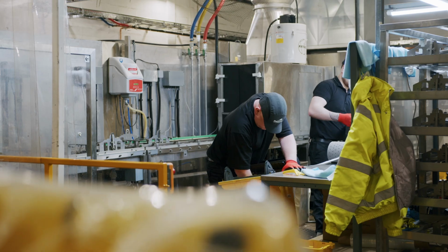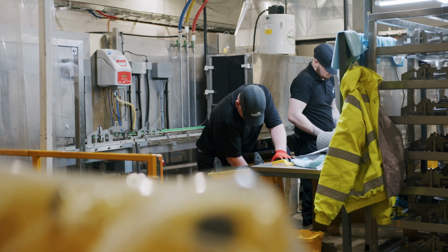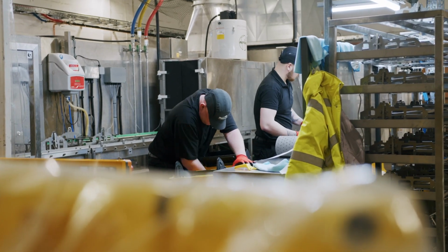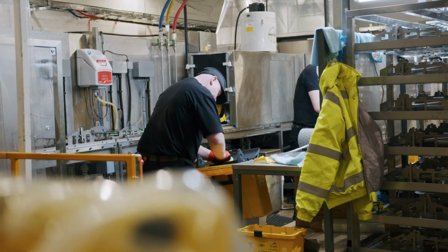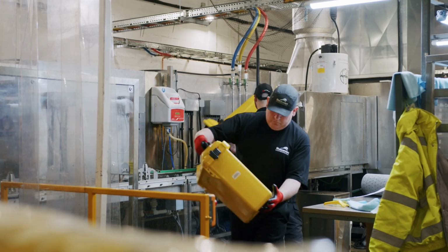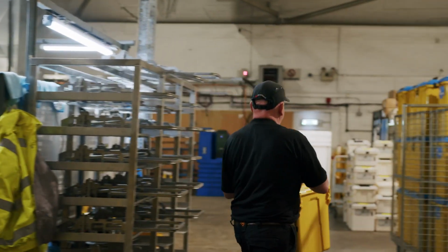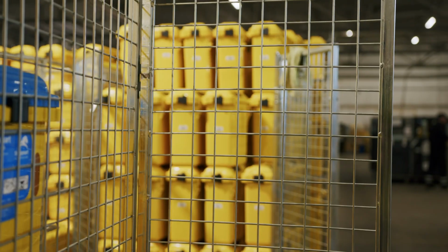And you can remove a minimum of 3 logs, commonly 4, sometimes up to 5, just with warm water and detergent and physical removing. Yeah, between 3 and 10 to the 5. But there's actually not a definition of cleaning that involves logs. You'll find research like mine that says this is what it can do, but everybody brings it back to just the visual look at it. But with disinfection, you'll find that the definition is a minimum of 4 logs for low-level disinfection.